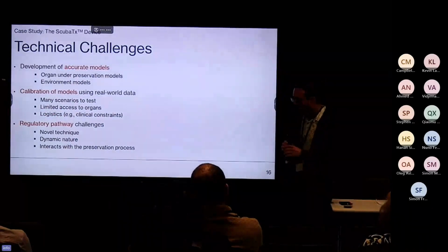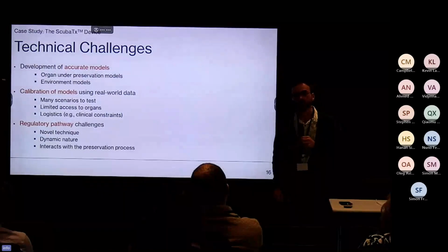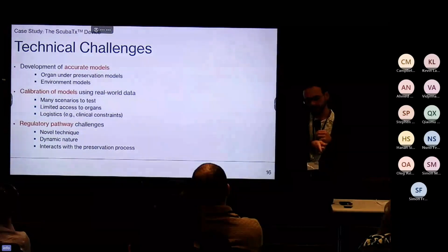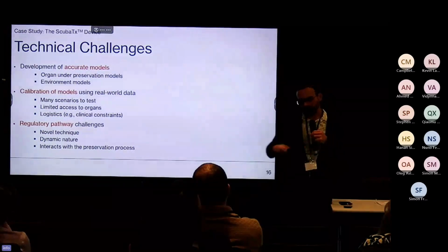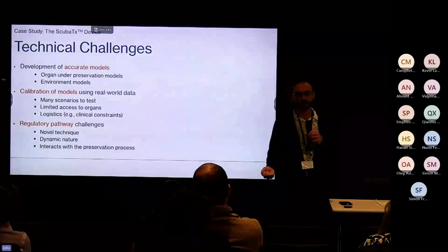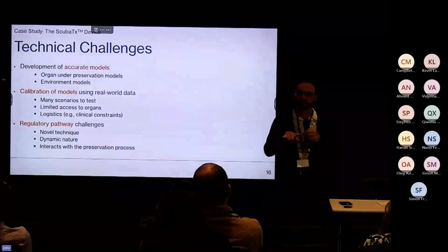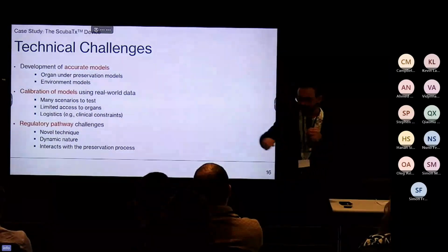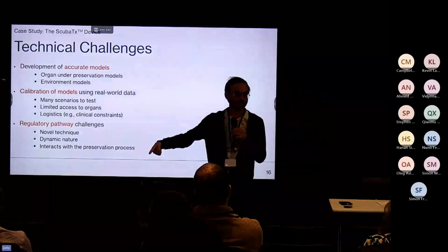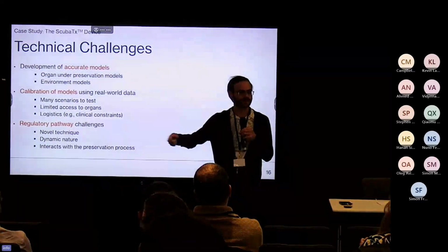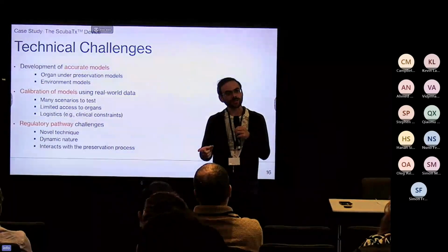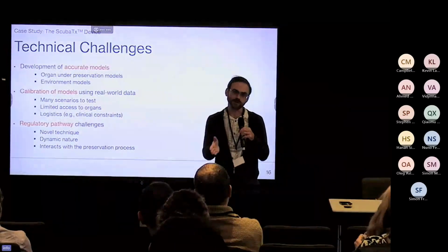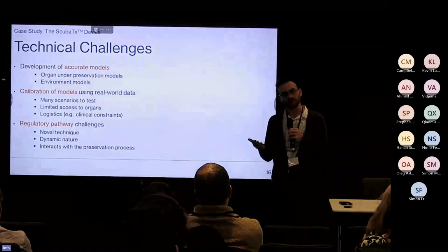The trouble with the challenges we've got are things like the accuracy of models, because, for example, the control software regulates pressure for the exit of the box, but the tubing to the organ and where the surgeon puts it into the organ will have a delta of pressure from the target pressure. So the PID controls for, say, 100, okay, the pressure that gets to the organ is what, 90, 80, 102? Well, it can't be more, sorry, but the point is, what happens if it sloshes around as you're moving things, right? So how do you account for that? In other words, it's not just PID control.